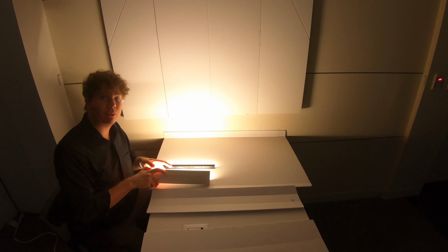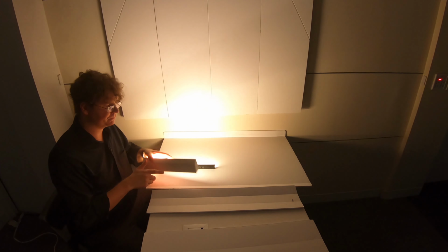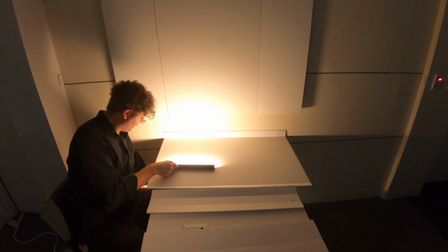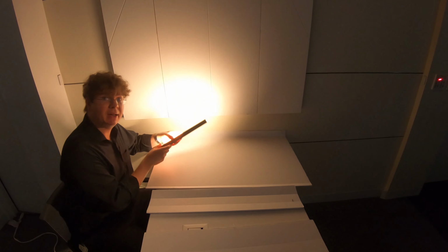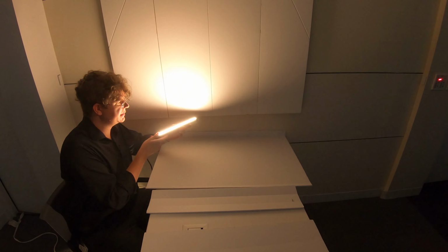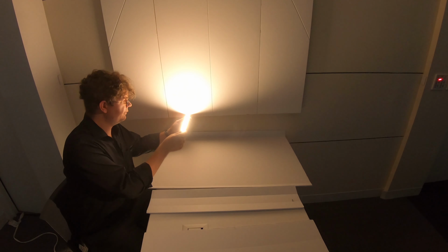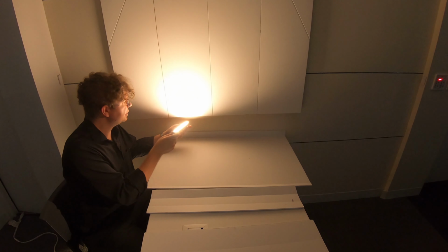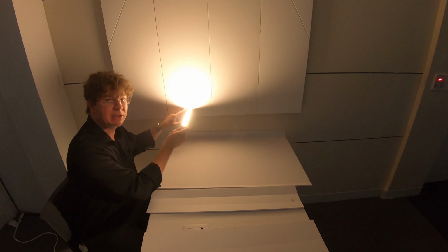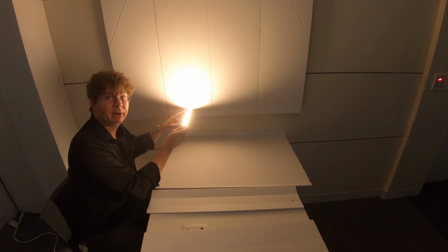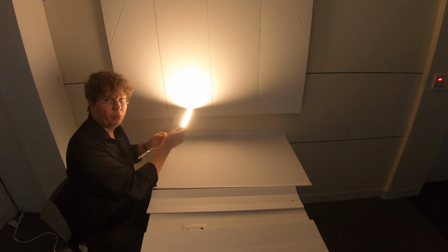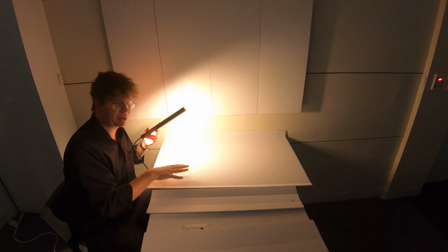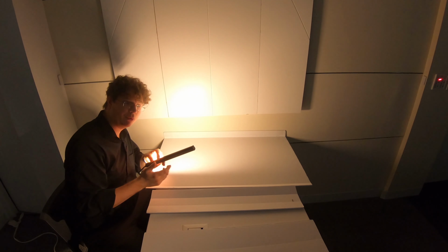Let's take a look at how we construct architectural coves. I'm going to start with a very bare bones cove light. So this is a 1-foot LED strip. It's essentially a tape light with light diodes spaced out every 6 inches. You'll see the distribution of light is just a very wide 160-degree blob of light. We depend on the construction of the architectural cove to shape the way light moves.